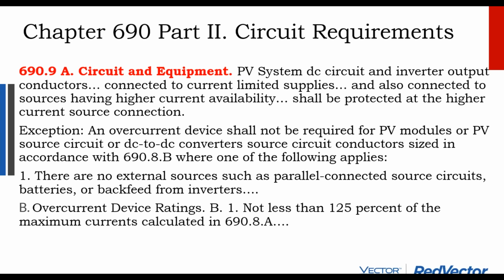But again, that all relates to the fact that it's not just your standard, oh, we need to allow additional ampacity in our conductors so that they don't burn up, but also we need to allow additional ampacity because the listing condition of the solar panel is not what it's going to perform in the field. Whereas all other devices, a 1,000-watt microwave is going to use 1,000 watts, whether it's in Canada or Texas. Not so with a solar array.